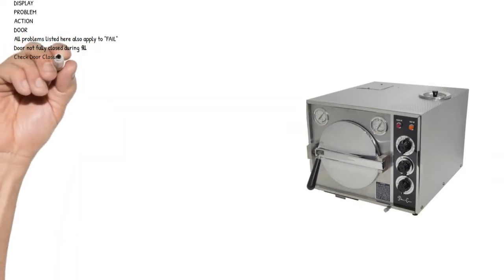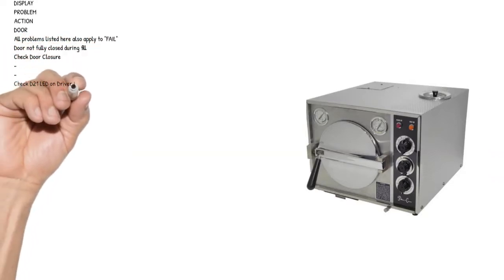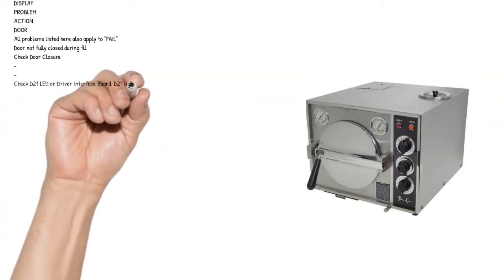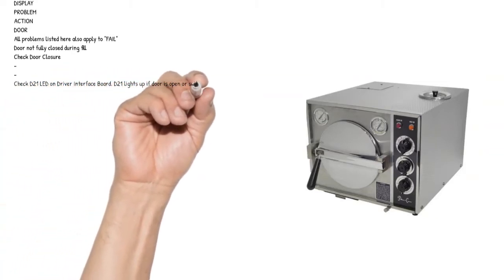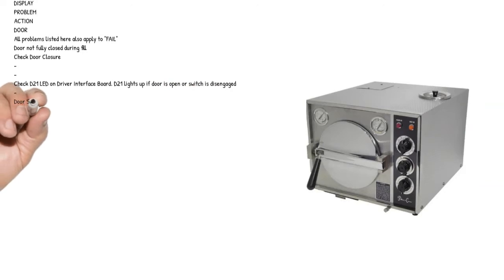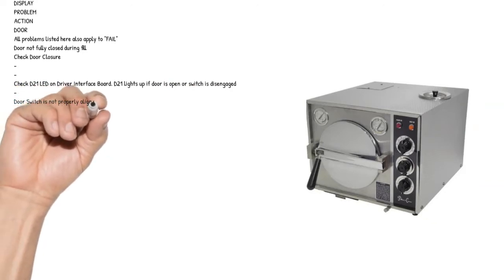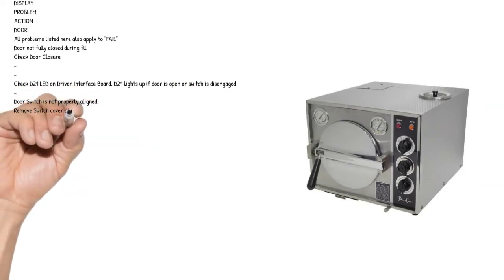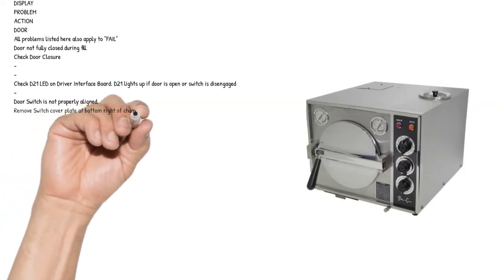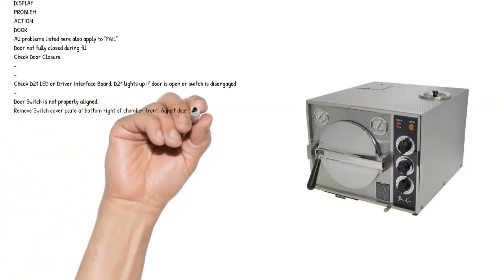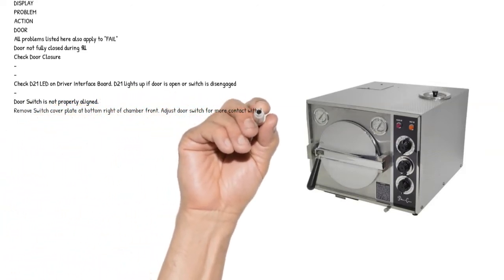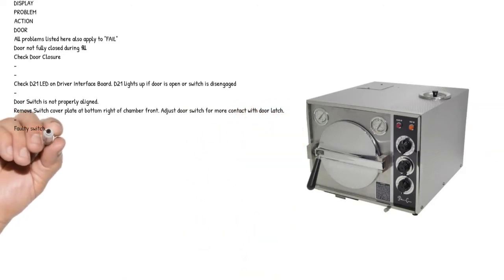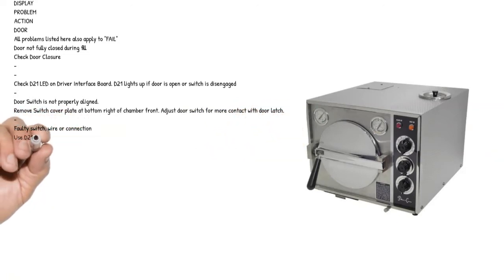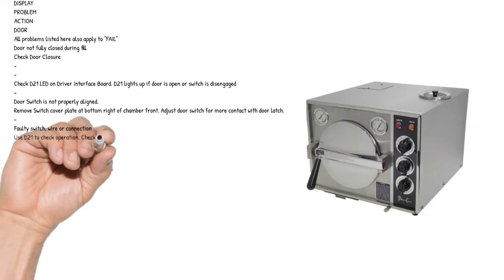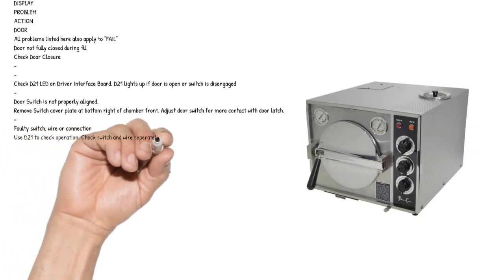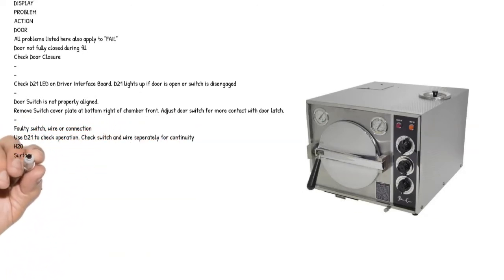Door not fully closed during fill. Check door closure. Check D21 LED on driver interface board. D21 lights up if door is open or switch is disengaged. Door switch is not properly aligned. Remove switch cover plate at bottom right of chamber front. Adjust door switch for more contact with door latch. Faulty switch, wire or connection. Use D21 to check operation. Check switch and wire separately for continuity.